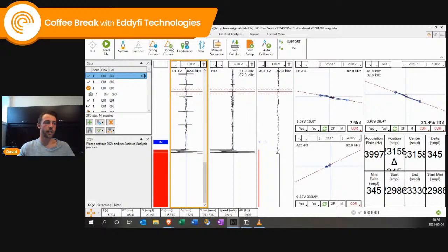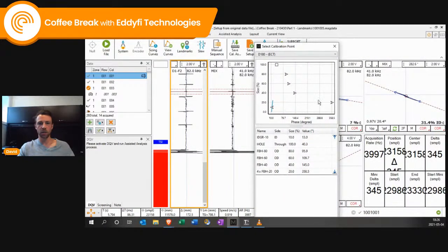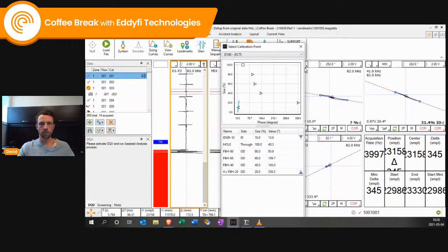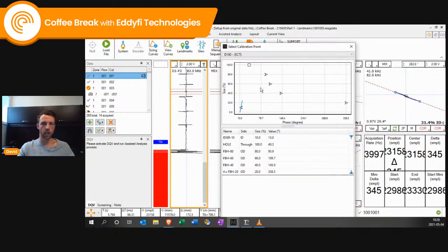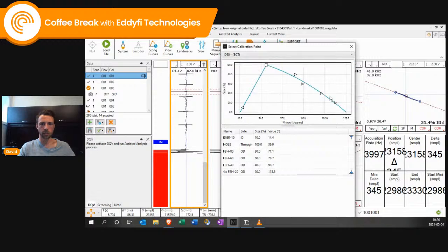We could look at this for quite a while. We could discuss again, but sometimes when it fails, we always advise to click on view curves. If you click on view curves, you will have those curves and the dots. What we want is nice lines. This one is a little bit off because of that defect. The system is not able to draw a line to set those calibrations.